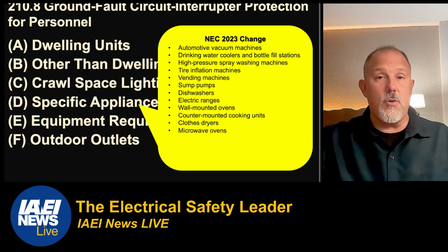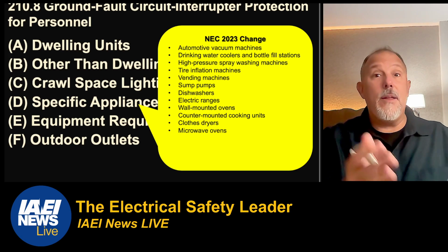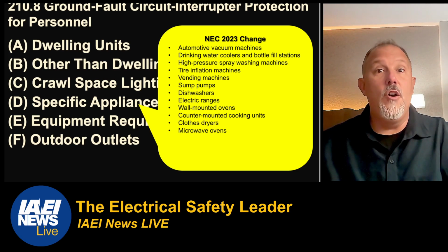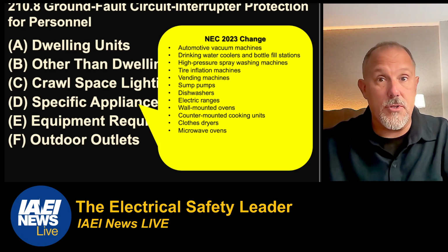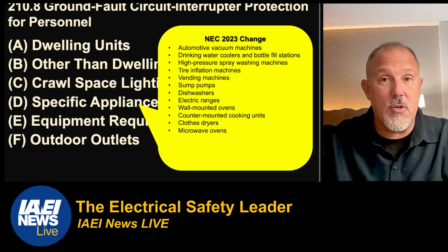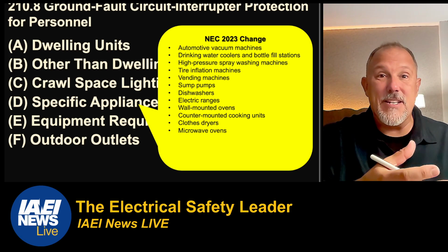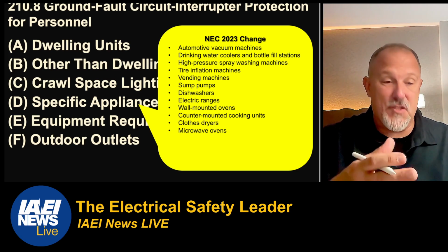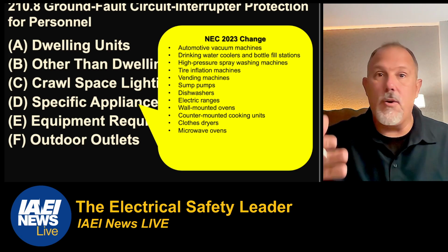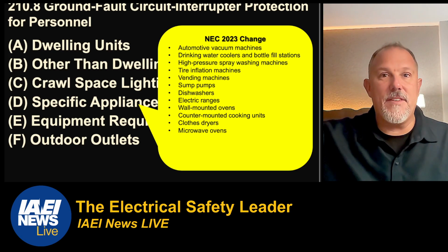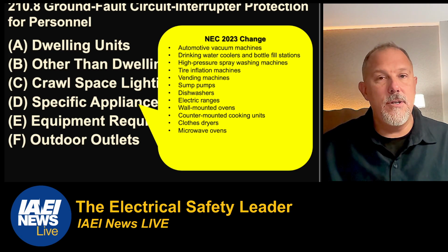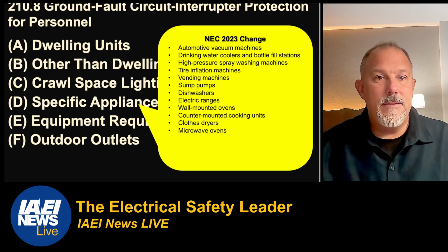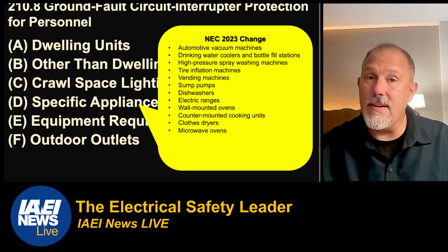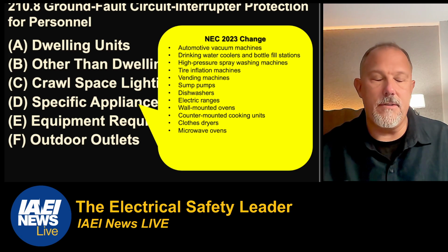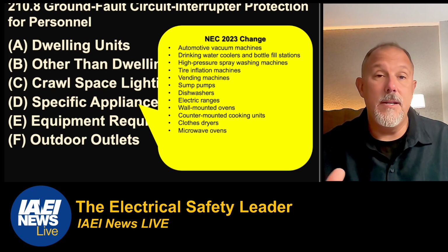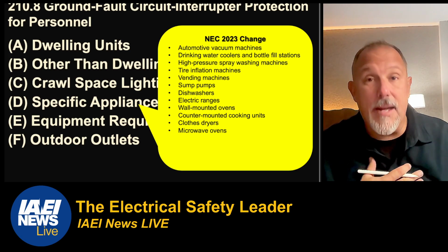We have a receptacle requirement for that equipment. And what do we have? GFCI protection for those who are working on it with tools, who are going to be plugging into that receptacle, working on equipment that's required to be serviced, have space for servicing, HVAC equipment and others. We have to have GFCI protected receptacles. Well, this is no different. Very similar. I wouldn't say different, no different. It's not exactly the same, but it's very similar, in my opinion.